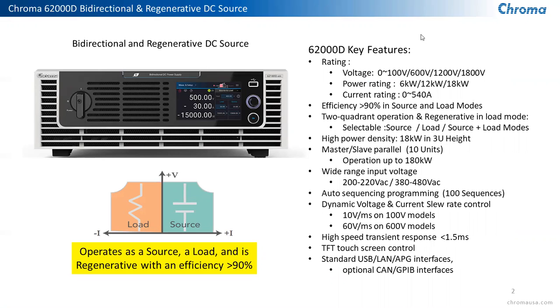So our 62000D family of products has multiple units ranging from 100 volts up to 1800 volts in four different voltage types. It also ranges from 6 kilowatts up to 18 kilowatts in the different model types. We can achieve currents all the way up to 540 amps with our 18 kilowatt 100 volt unit. Efficiency on this unit is greater than 90%, which is amazing. And based on that efficiency and the fact that it is regenerative as a load, we're able to condense this unit down into a 3U total height package at 18 kilowatts.